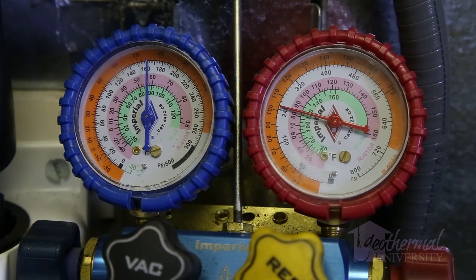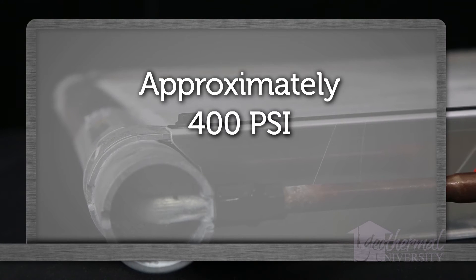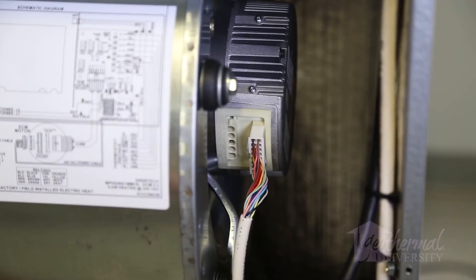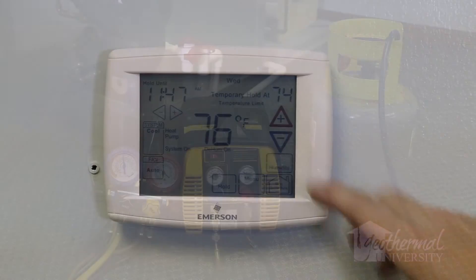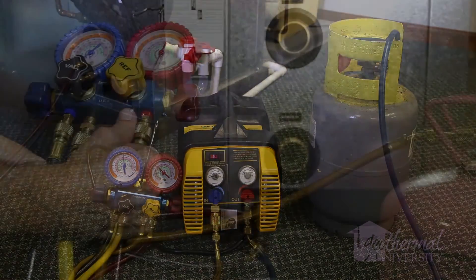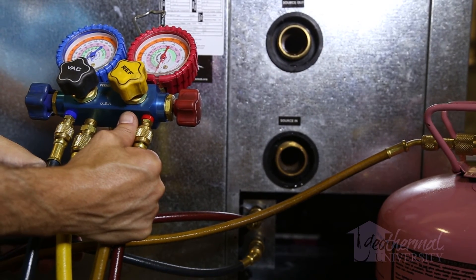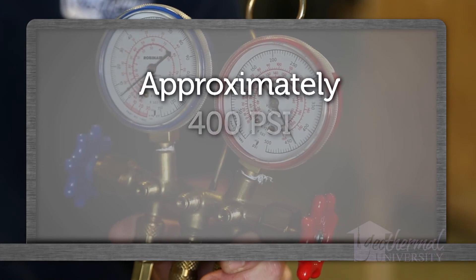It is helpful to build a maximum pressure inside the evaporator coil. A heat pump evaporator coil will see pressure nearing 400 psi in heating mode with a full charge. If the unit is operational, disable the evaporator fan and run the unit in heating. If the unit has lost significant refrigerant or is not operational, you can build significant pressure in the coil using dry nitrogen or helium. Pressurize the entire system to about 400 psi.